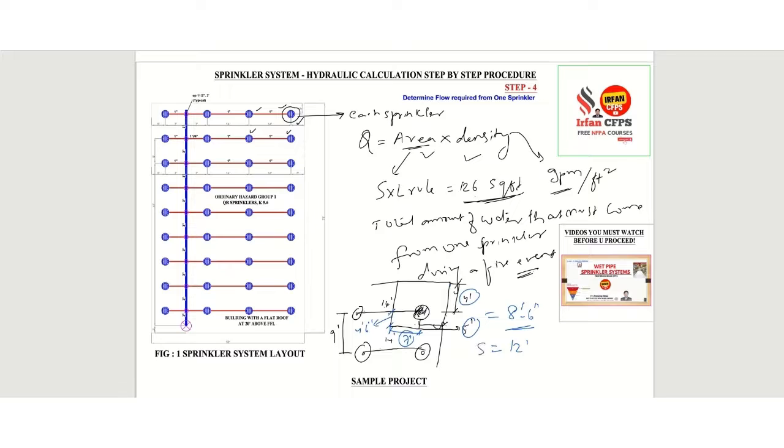Here S will be 12 feet, L will be 8 feet 6 inches. In actual scenario, this will be the coverage area for this particular sprinkler. If you calculate 12 feet multiply by 8 feet 6 inches, then we will get around 102 square feet.